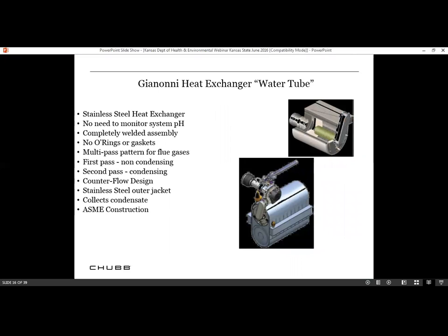In the industry right now, there is a heat exchanger made in France called Gianonni. It's a water tube heat exchanger. It is stainless steel. There's no need to monitor the pH level. This is a hot water system, but this boiler here will have about 5 gallons of water. It's a closed loop system. It's completely welded assembly. There's no O-rings or gaskets. It's multi-pass pattern for flue gas. There is a first pass non-condensing, which is at the very top where the burner is, and I've got a slide that'll show that. Then the second pass is condensing. It's counterflow design, stainless steel outer jacket. It collects the condensate and puts it to a drain, and they're ASME National Board certified, constructed.